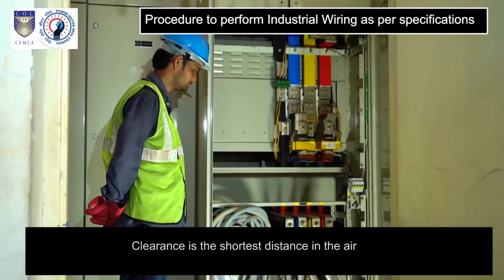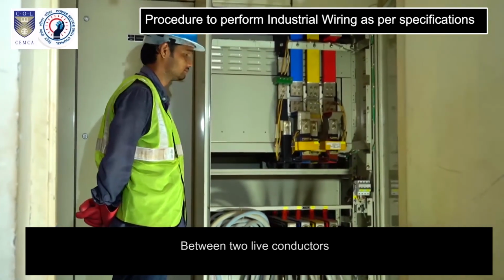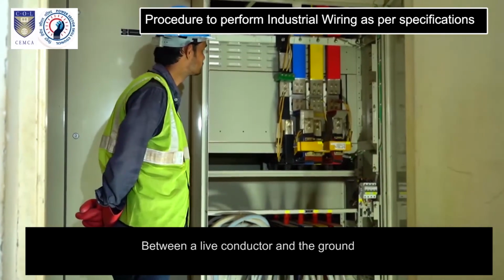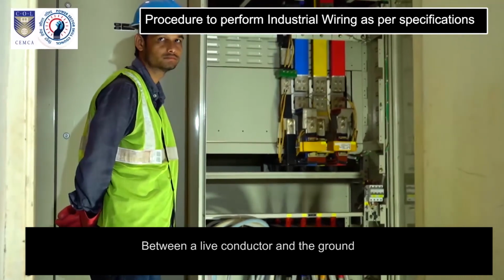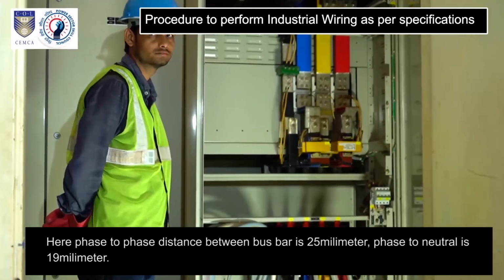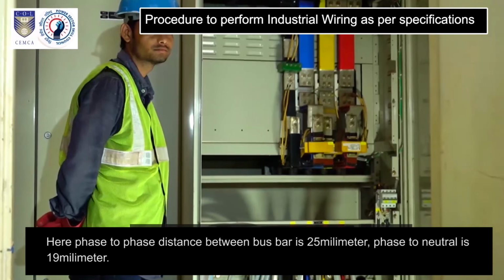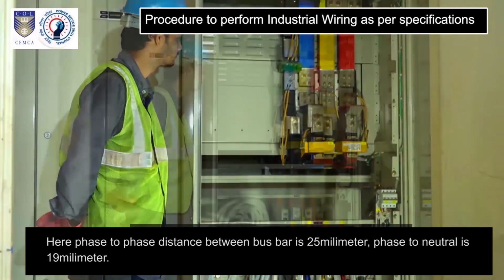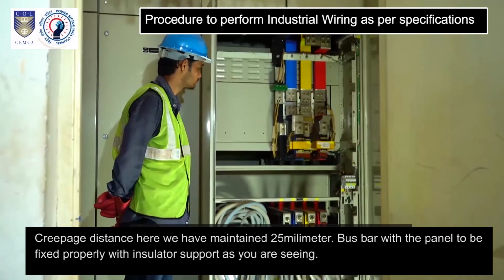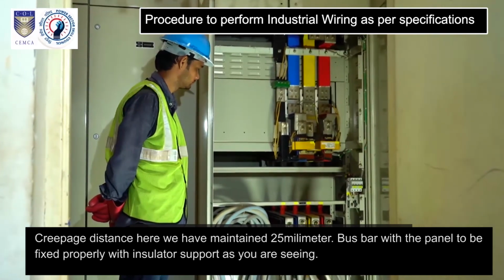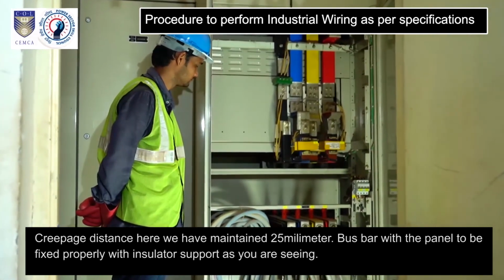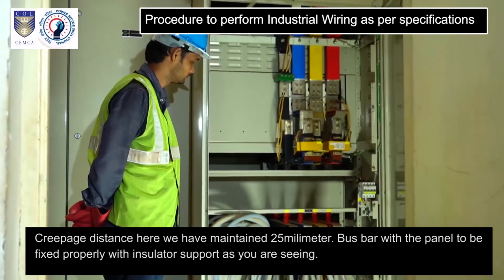Clearance is the shortest distance in the air between two live conductors, between a live conductor and the ground. Here phase-to-phase distance between busbar is 25 mm. Phase to neutral is 19 mm. Creepage distance here we have maintained 25 mm. Busbar with the panel to be fixed properly with insulator support as you are seeing.